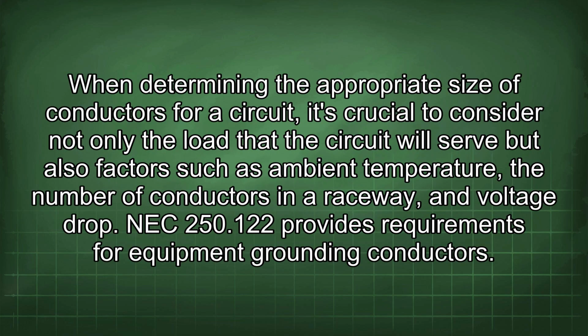When determining the appropriate size of conductors for a circuit, it's crucial to consider not only the load that the circuit will serve but also factors such as ambient temperature, the number of conductors in a raceway, and voltage drop. NEC 250.122 provides requirements for equipment grounding conductors.